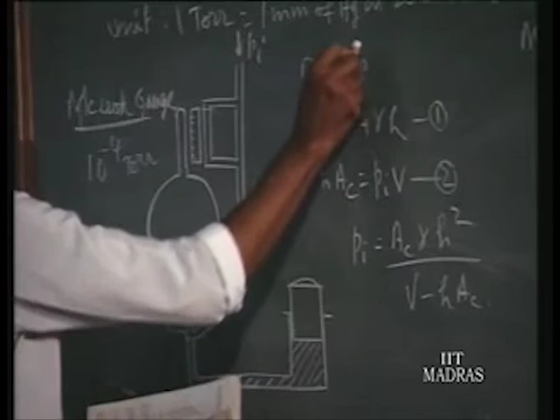The principle is like this. Here we have a plunger and cylinder assembly. Mercury is filled up there. By withdrawing the plunger up, we can bring the mercury column down into this capillary. These are capillary tubes, with a spherical bulb connected. When you withdraw up to this point, the vacuum pressure can enter into this volume and the capillary tube.